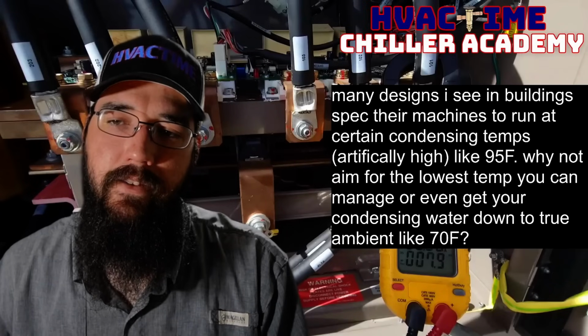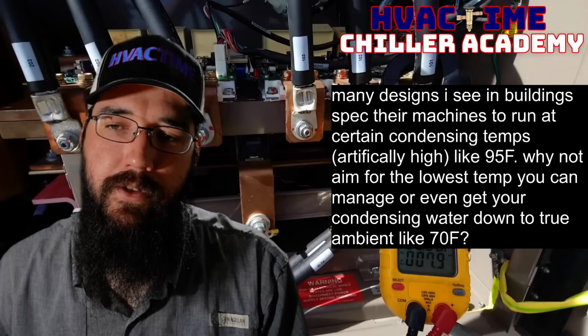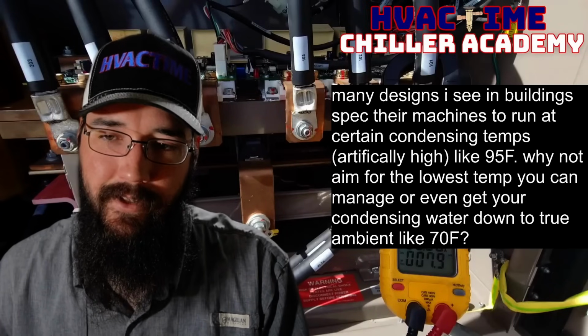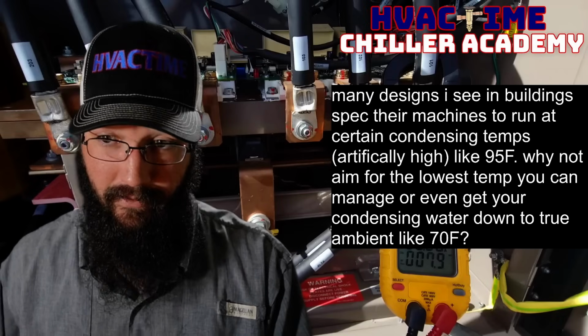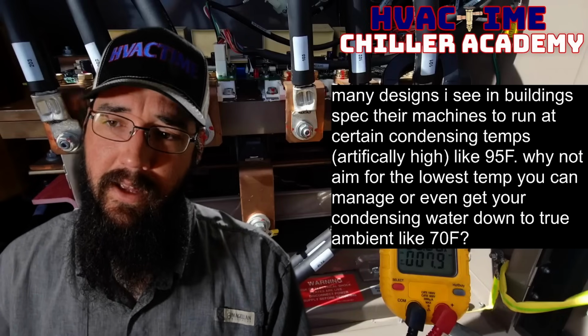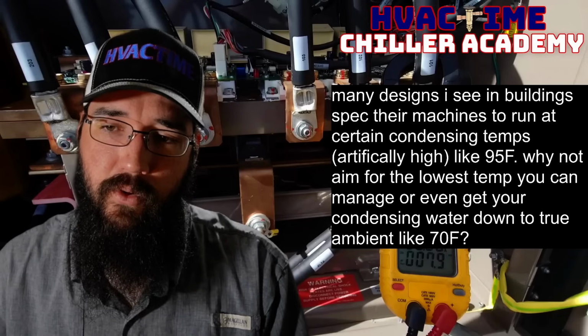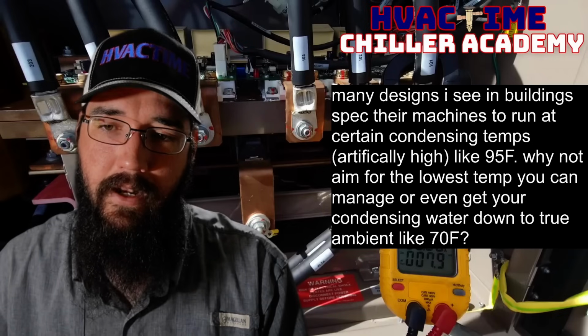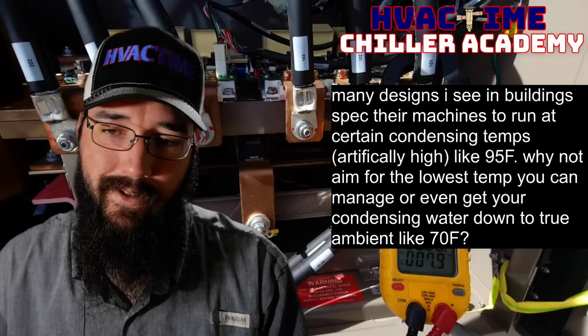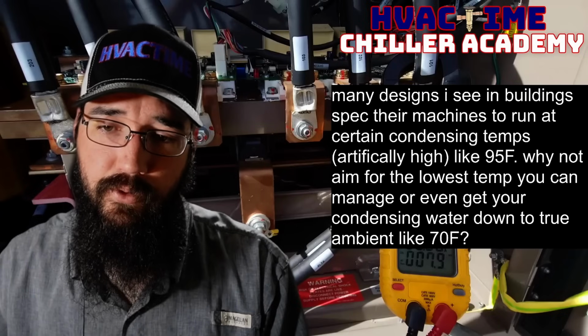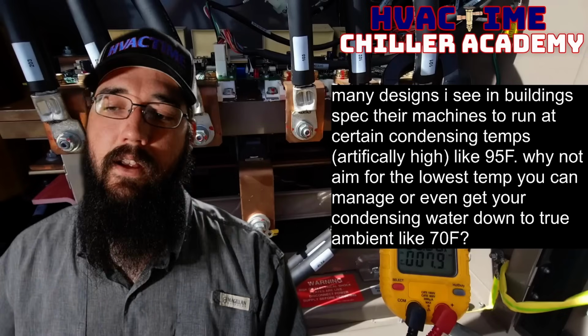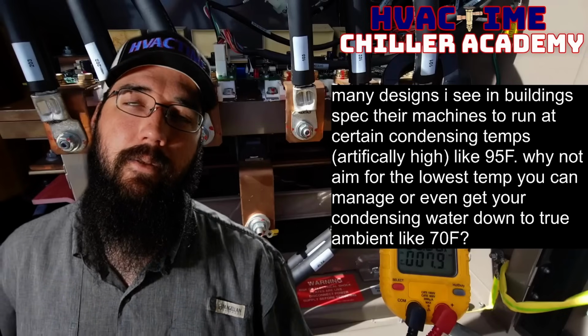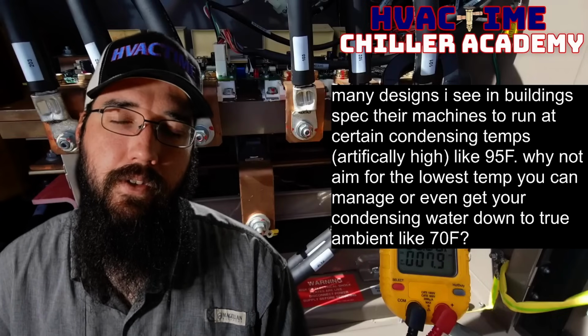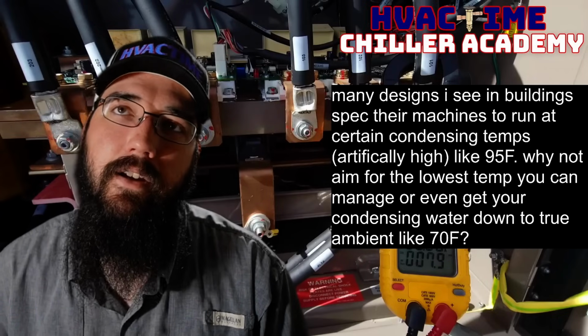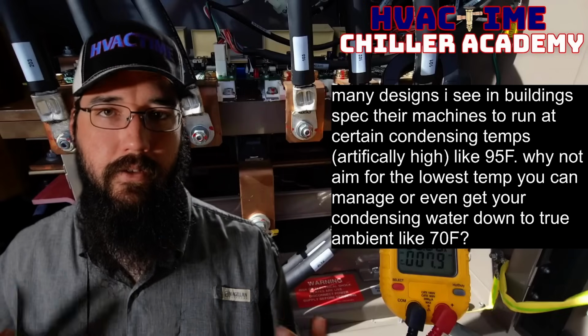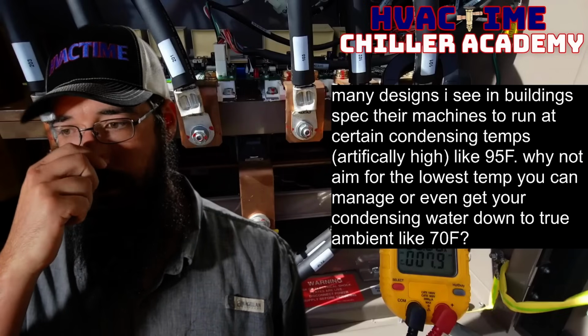Many designs I see in buildings spec their machines to run at certain condensing temps, artificially high, like 95. Goodness, 95 degrees. Why not aim for the lowest temp you can manage, or even get your condenser water down to true ambient, like 70? This is a very good conversation, and the opinions around it could go a few ways.